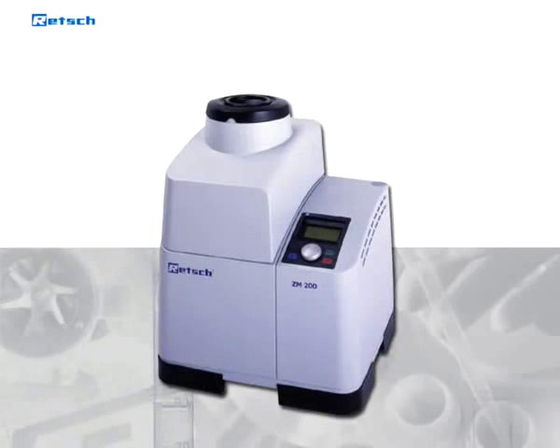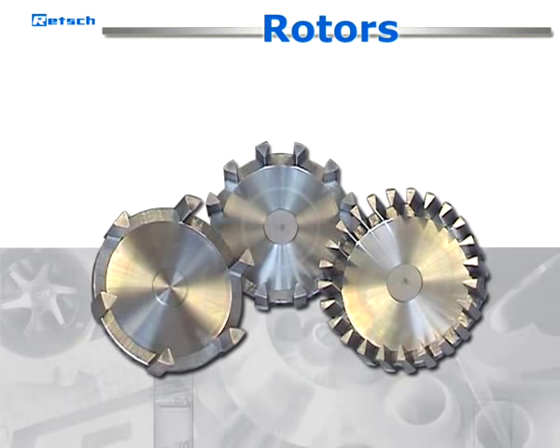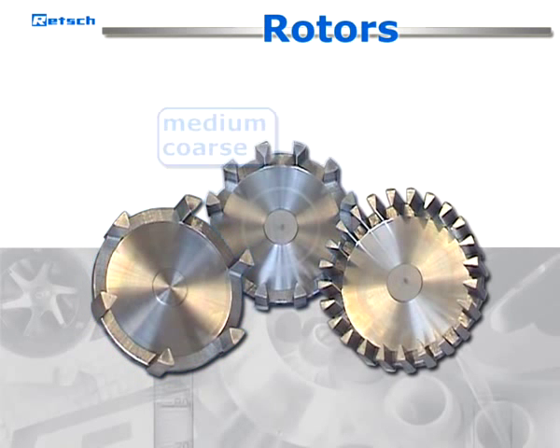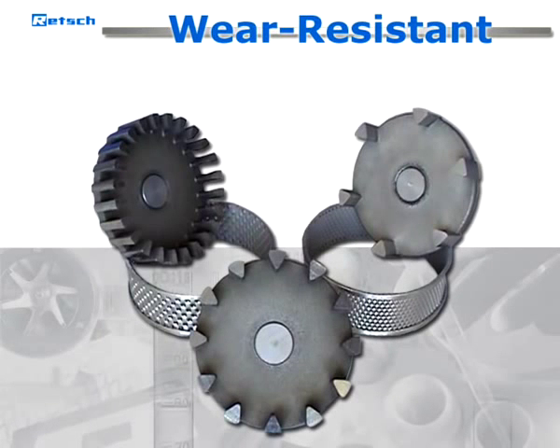Furthermore, Retsch offers a wide range of accessories to suit the instrument to the variety of applications. For example, rotors with different numbers of teeth: one for coarse, bulky and fibrous materials; one for medium coarse materials; and one for fine materials. Distance sieves for temperature sensitive and brittle materials. Rotors and ring sieves for heavy metal-free size reduction. Rotors and sieves with wear resistant coatings for abrasive samples.